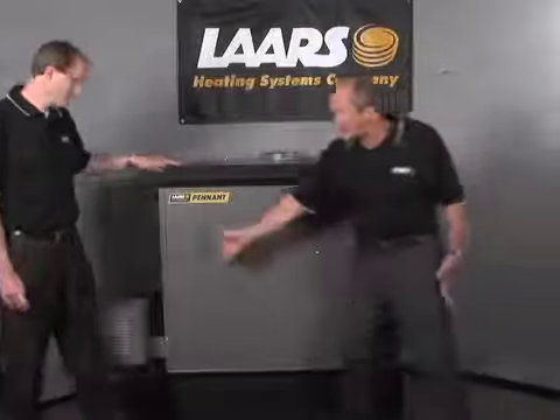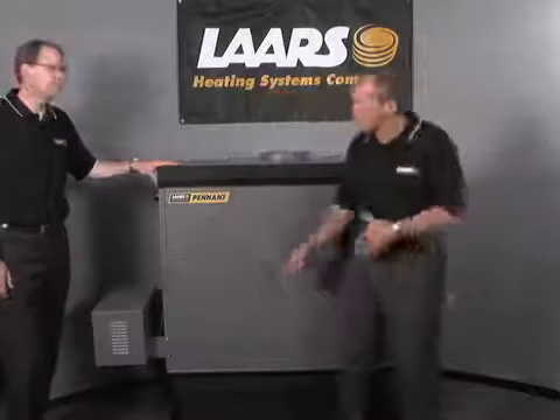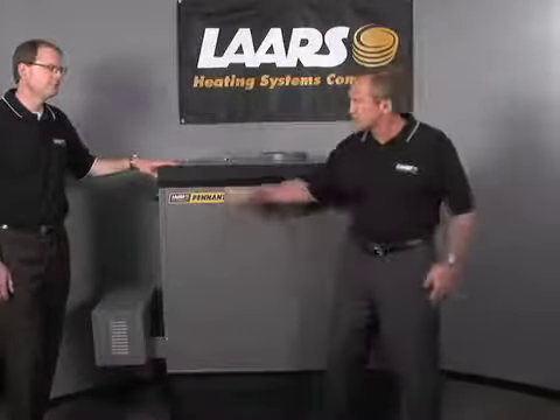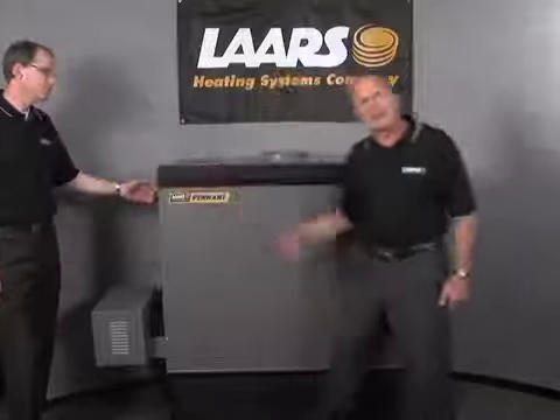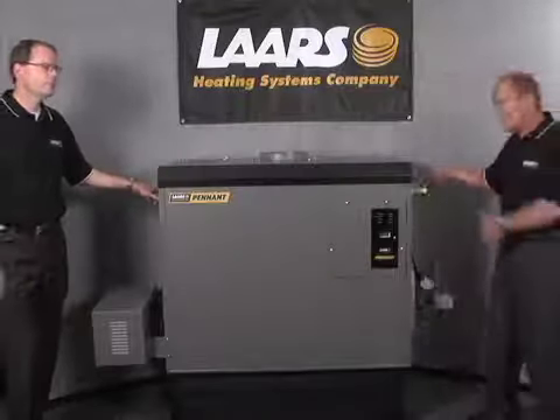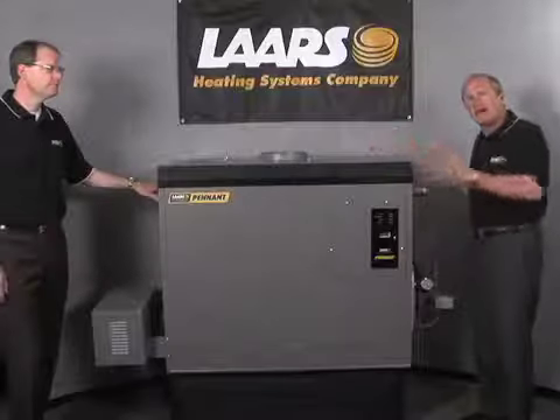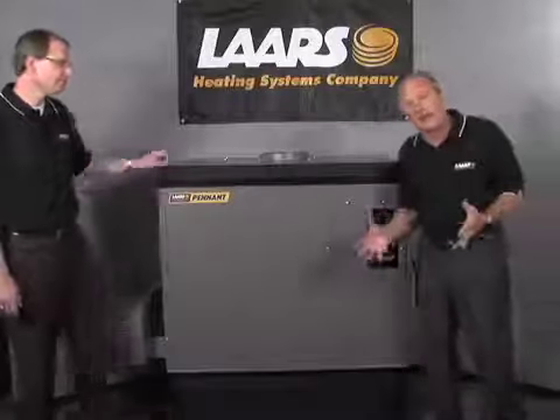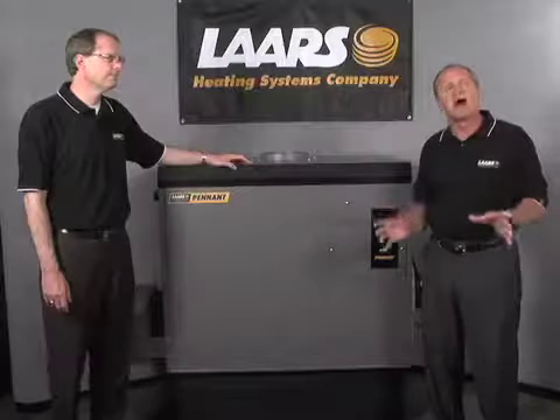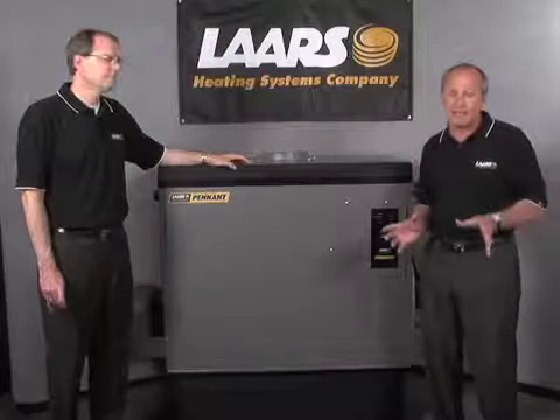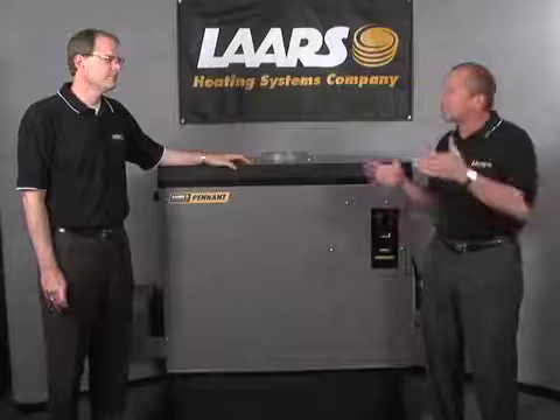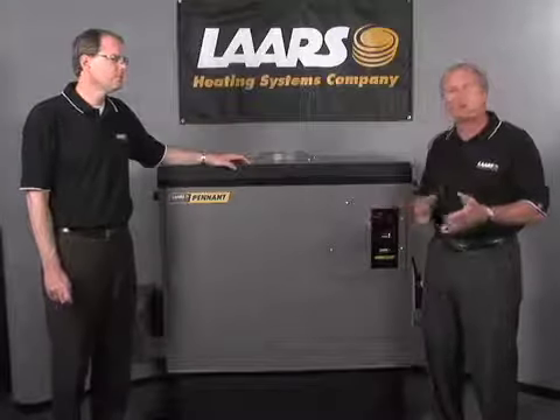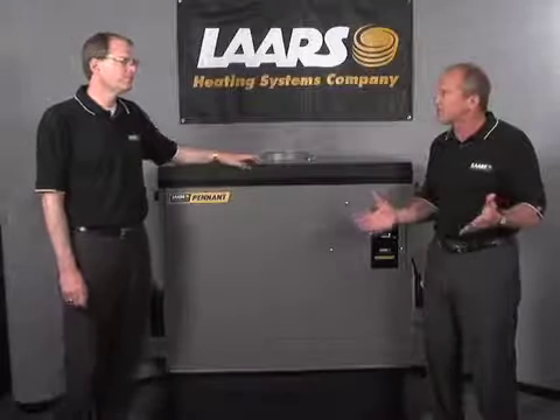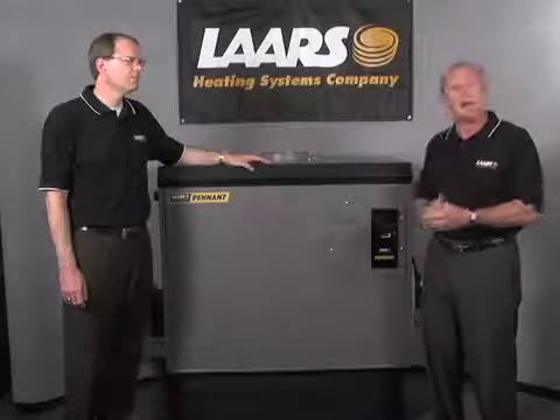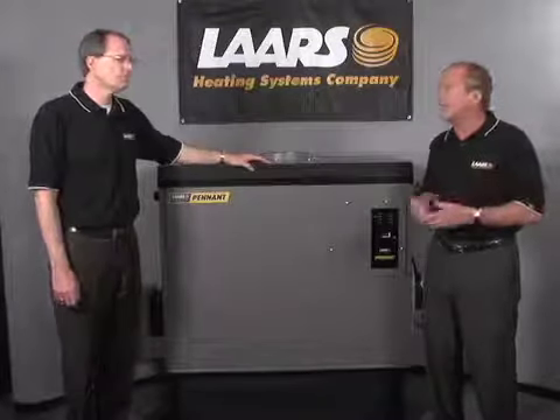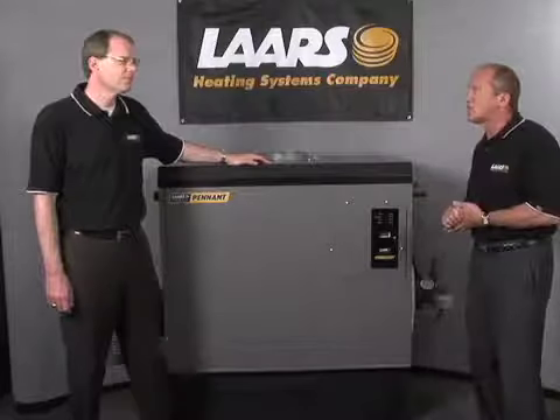We have a pump mount on this side of the unit, and we can switch our gas connections. You see the cap on this end. We can take that cap and put it on this side. We can take this valve and move it over to that side, and we can easily install this product with really symmetric piping, both on the gas side and the water side. So from that standpoint, I want to turn it over to Tom. He'll talk about some more features, the stage firing that this product does, all the way up to 2 million BTUs. And again, we take it up from 199 all the way up to 2 million. So Tom, why don't you take over and talk about some of that?